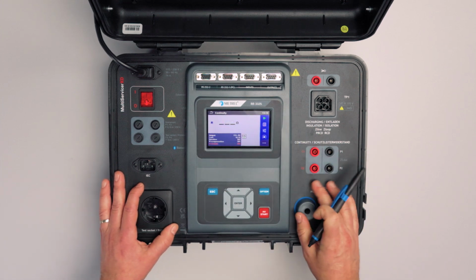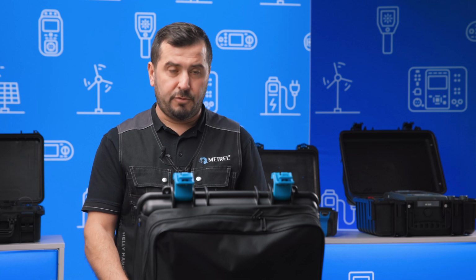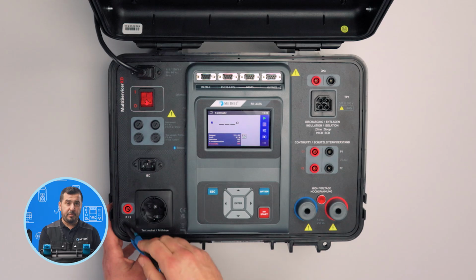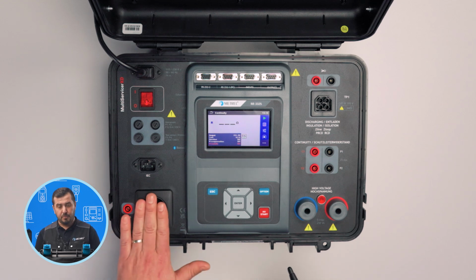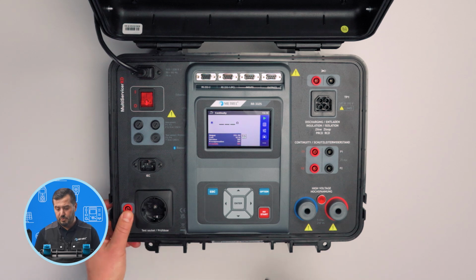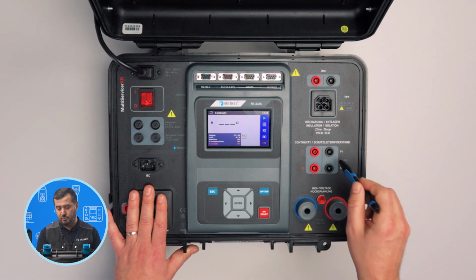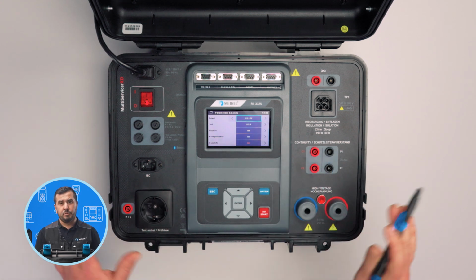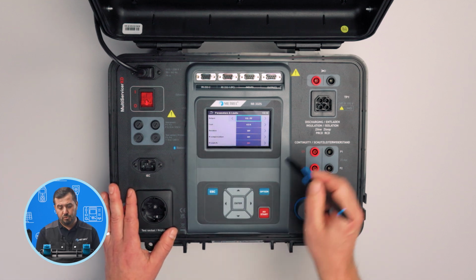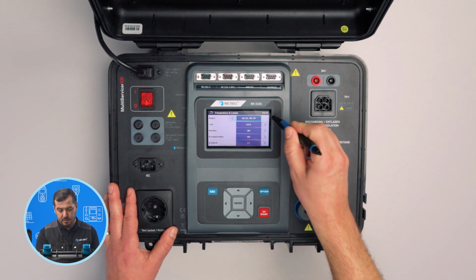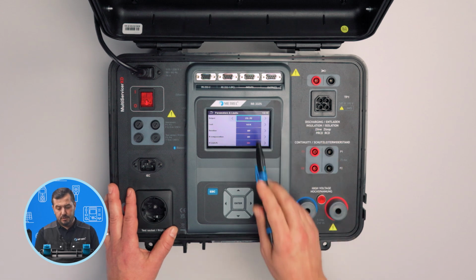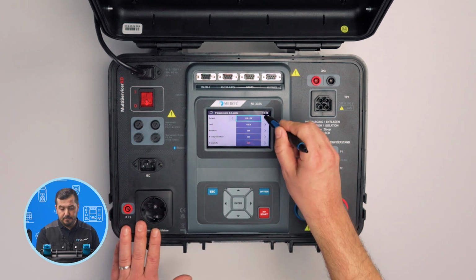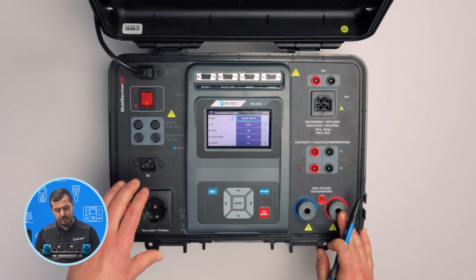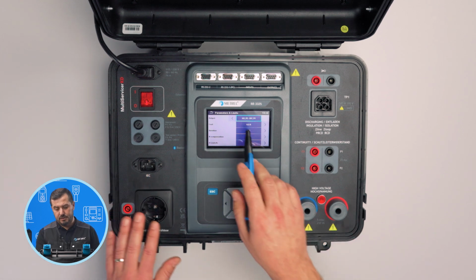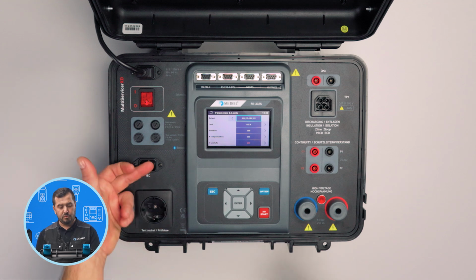The next in the line is the earth continuity test. The instrument supports different current levels for execution of the earth continuity test, as well as two different methods. One method, the two-wire method, is performed between main test socket P and the PE probe, and the four-wire test method is performed via this test terminal. How we choose where it is performed is here in the setting output, where we can use either the four-wire test method or the PE test method, which is performed here. Then an additional option is for testing only the IEC leads or the extension leads, and this is the option here, where the test will be performed between these two test terminals.